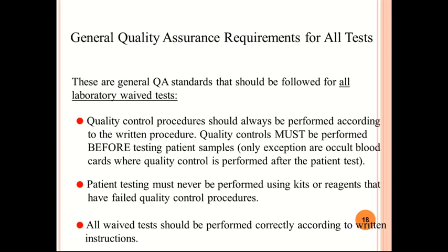These are general QA standards that should be followed for all laboratory waived tests. Quality control procedures should always be performed according to the written procedure. Quality control must be performed before testing a patient sample. Typically, most healthcare facilities will do their quality controls first thing in the morning before the clinic even opens. Patient testing must never be performed using kits or reagents that have failed quality control procedures.